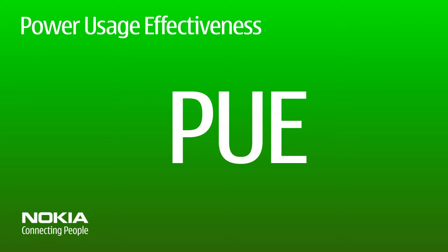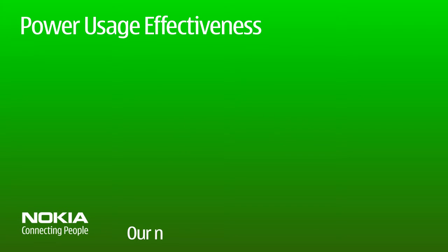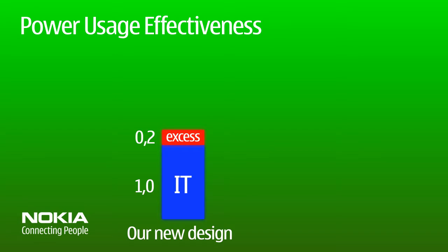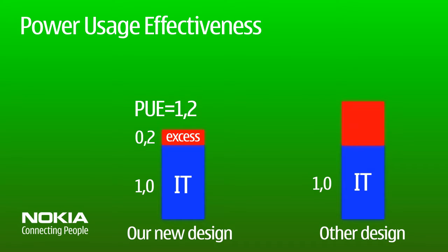All these actions are steps towards a power usage effectiveness factor of 1.2, which means that for every watt of energy going into the IT equipment, we only need 0.2 watts of excess for maintaining the infrastructure of the data center, including cooling and lighting systems. In other designs, the excess can be up to 1.4. In other words, our design will produce up to 7 times less excess energy.